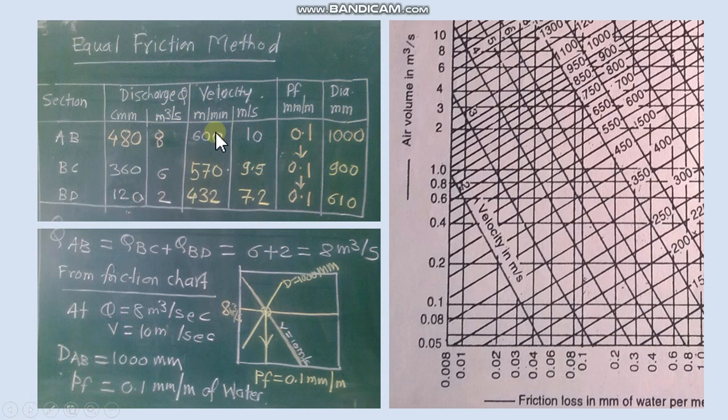In first duct, main duct discharge is given that we take in m³ per second. Now these are the remaining values that we will calculate in red color. So we start with the help of friction chart. From the friction chart for the main duct Q value and velocity value combination we get PF and diameter.